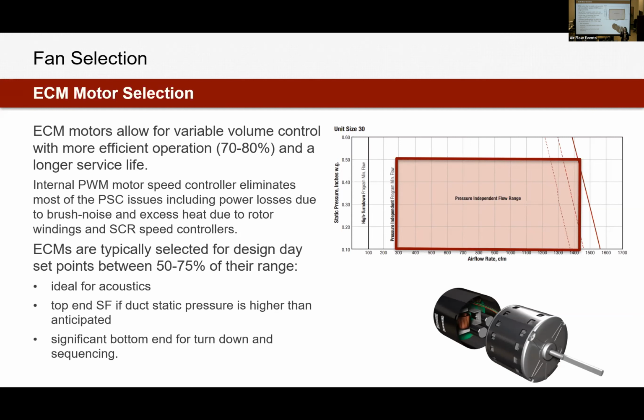So we can still hold a consistent airflow even if our filter's loading. That is pressure independent flow. The other program here is the bigger red box, high turn down flow program. This high turn down flow program, exactly as the name says, allows us to turn the motor down to 100 CFM. Doesn't matter the size of box, doesn't matter its top end, we can always get down to 100 CFM. I say 125 to be safe, but you're at about 100.